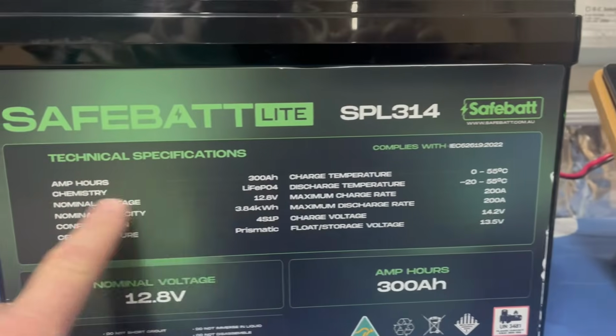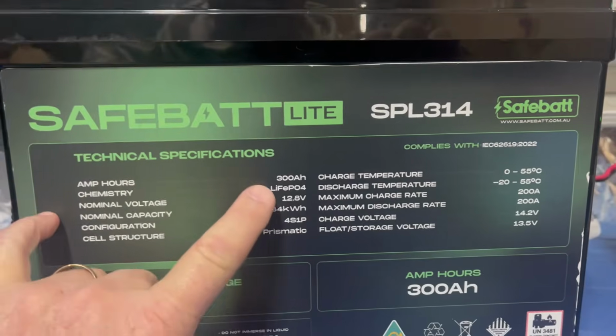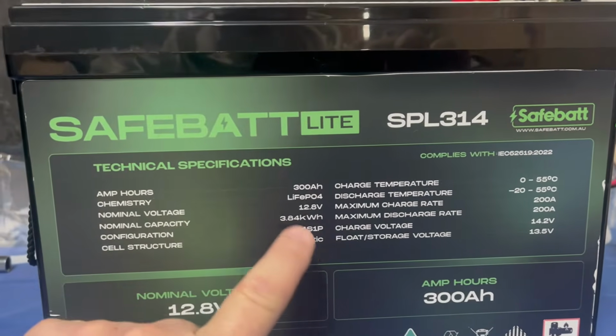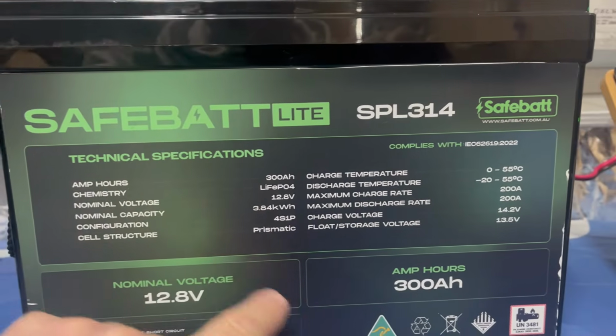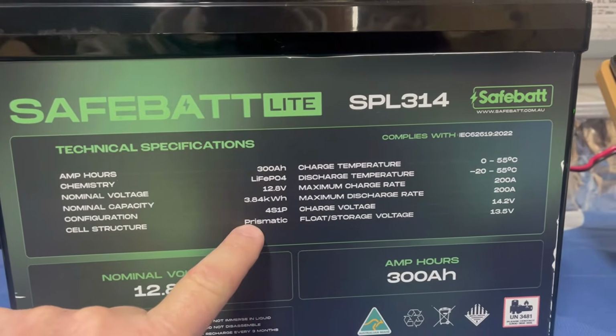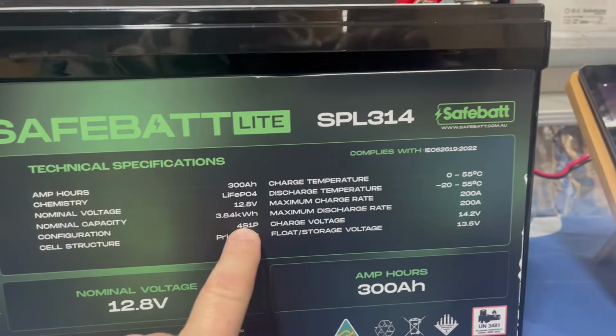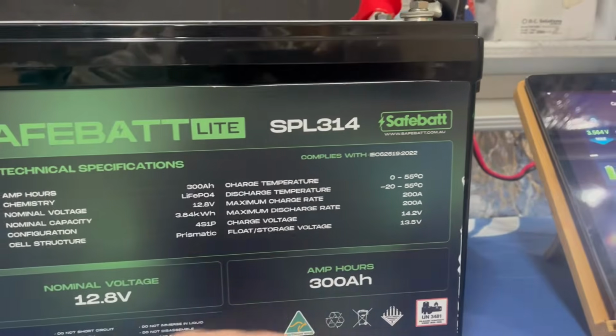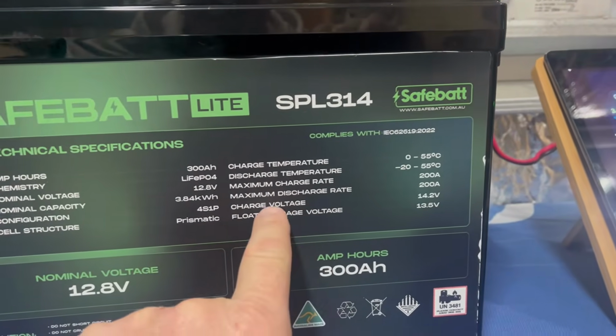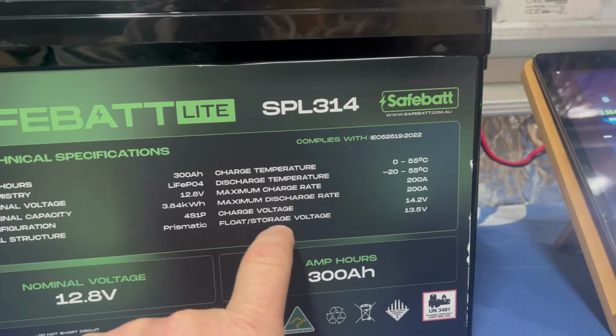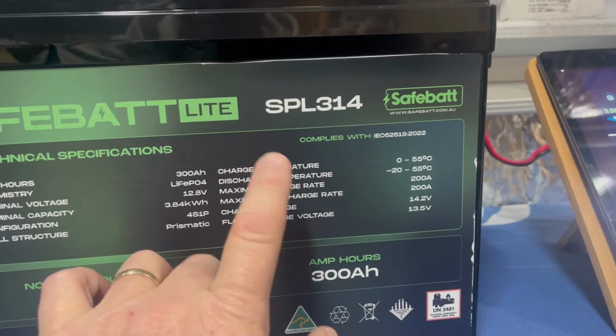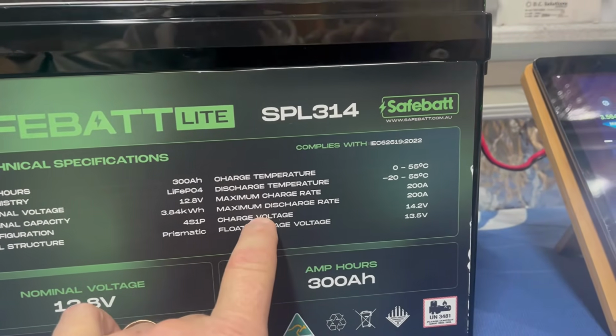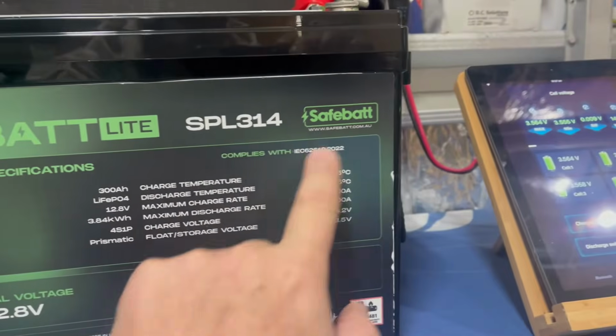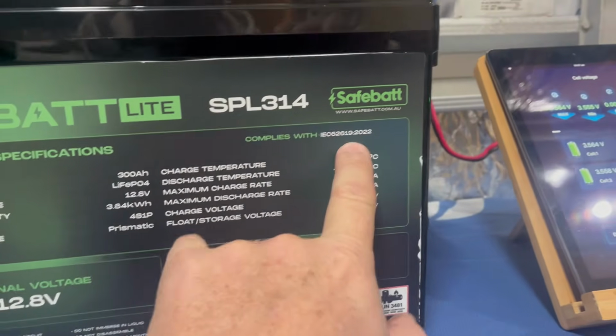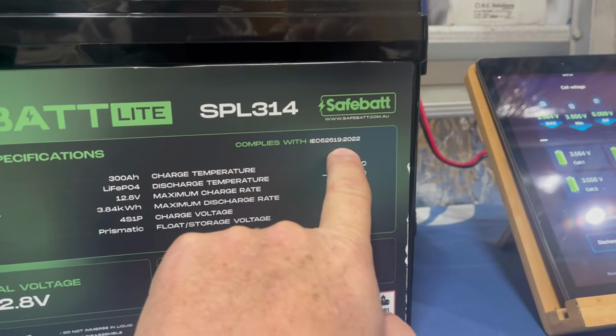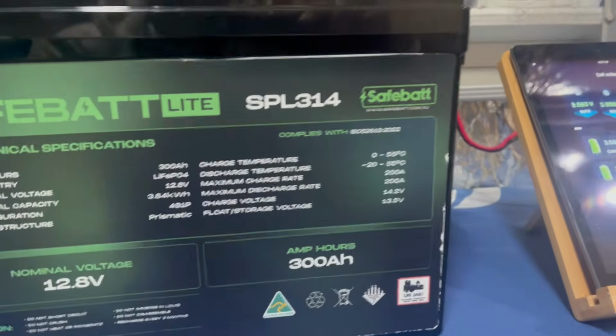Looking at the specs: 300 amp hour, LFP, 12.8 volts, 3.84 kilowatt hours. They're telling me it's a prismatic battery with 4S1P configuration, so 4 individual cells inside. Float and storage voltages of 14.2 and 13.5 all look normal, with a 200 amp charge and 200 amp discharge rate, and standard temperature ratings. It's also compliant with IEC 62619, which is very good.